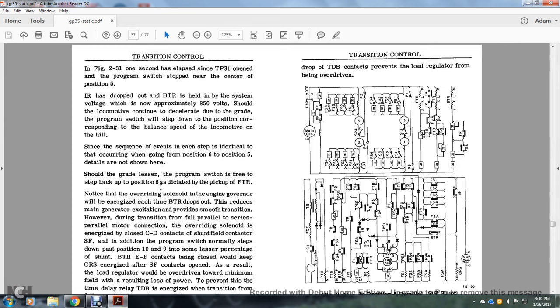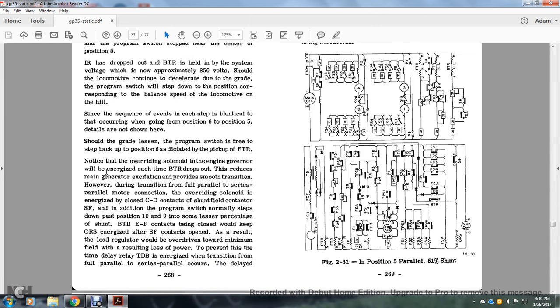Since the sequence of events occurs identically in going from position 6 to position 5, it is not shown here. Should the grade lessen, the program switch will step back to position 6, with the front transition relay picking up. Note that the overriding solenoid is energized with the back transition relay dropped, reducing the main generator excitation to provide for smooth transition.